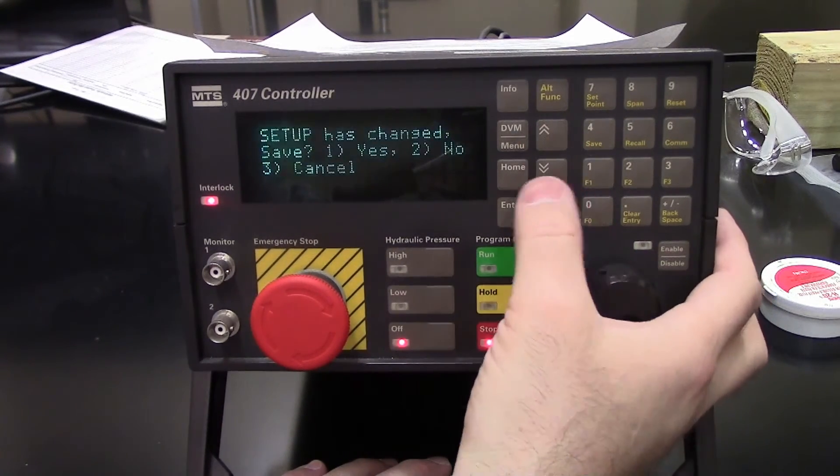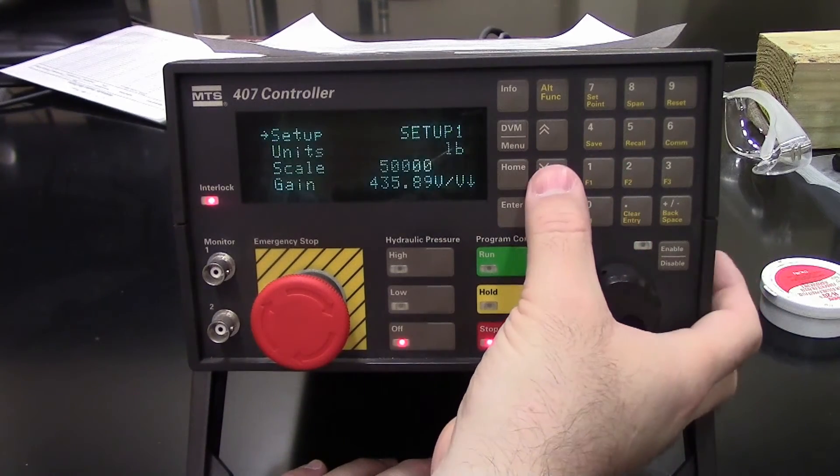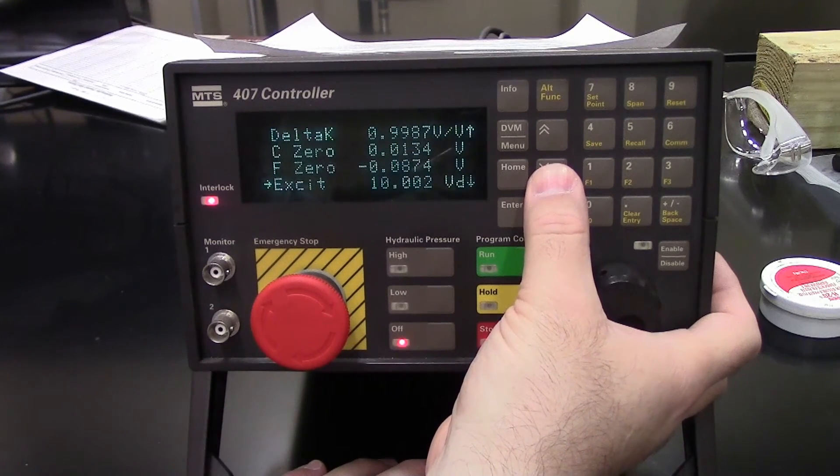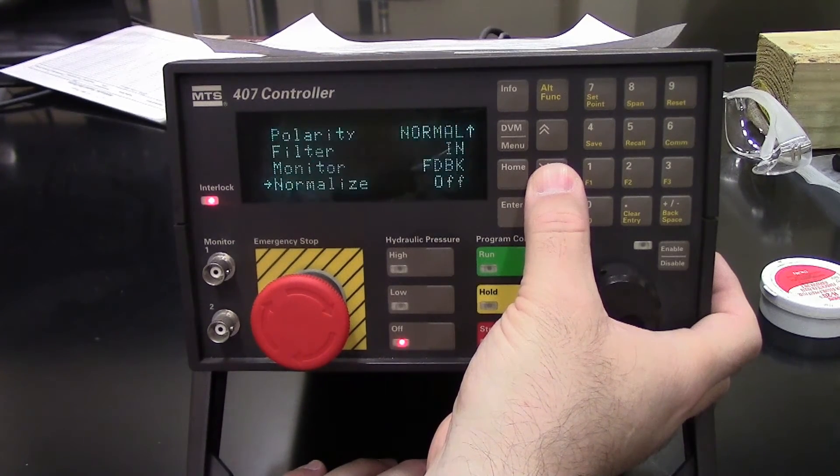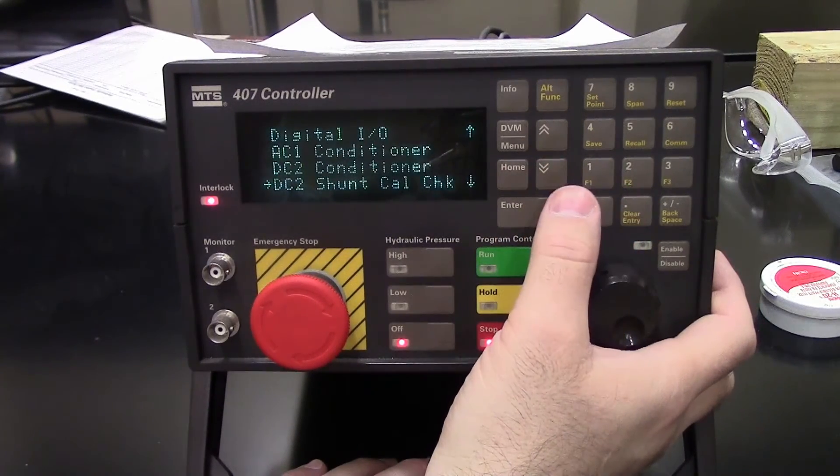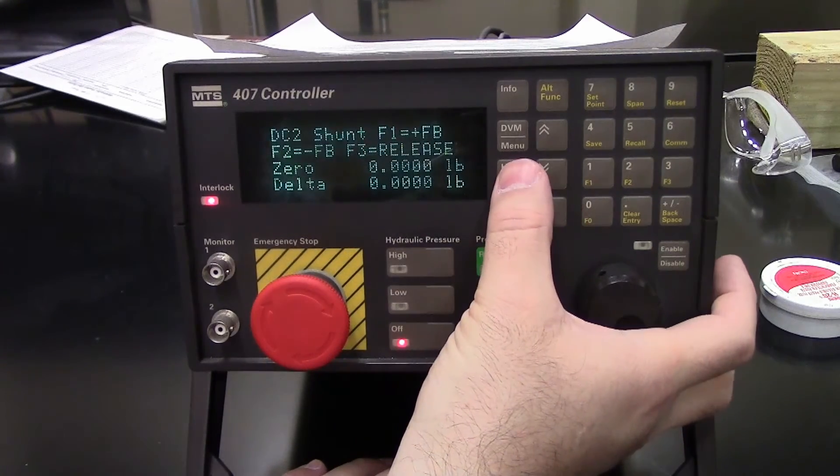We can bring up setup 1. There's the 50,000 pound scale. There's my gain. That will depend on your particular load cell that you've got. DC shunt calibration check. You can do a shunt calibration if you have your calibration resistors.